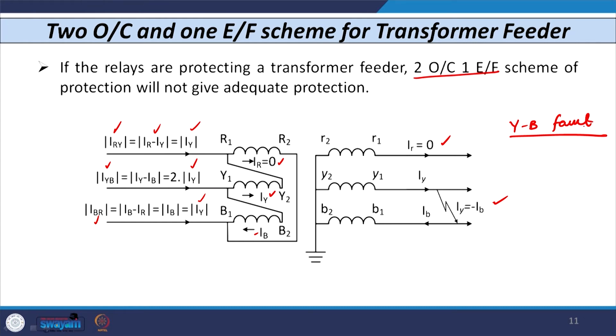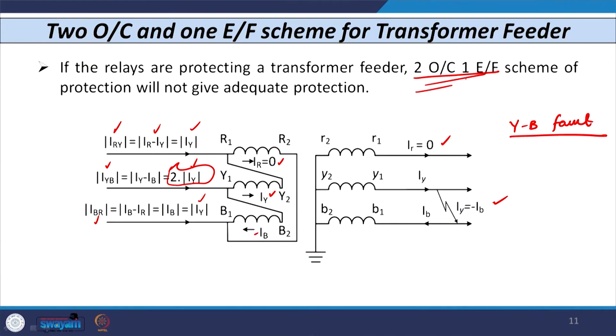You can see that a Y-B fault occurs, and we have removed the phase unit from Y phase, yet in Y phase the magnitude of current is 2 times the normal current. So 2 times the magnitude of IY flows in the Y phase from which we have removed the unit. There are chances of delayed operation, and our objective is to achieve instantaneous operation as soon as a fault occurs. This is not possible with the two overcurrent, one earth fault scheme instead of the three overcurrent, one earth fault scheme.